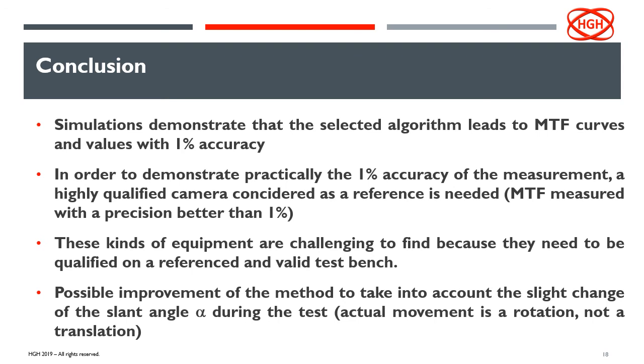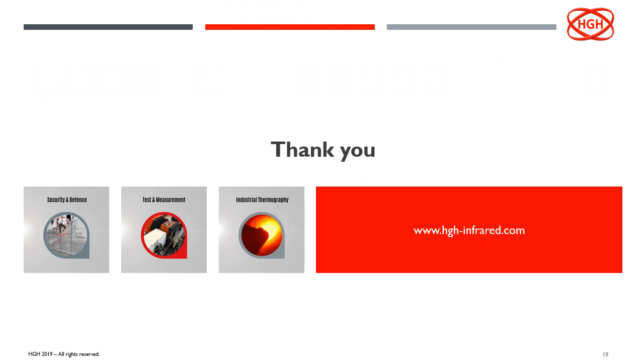In conclusion, simulations demonstrated that the selected algorithm leads to MTF values with 1% accuracy, confirming the method is valid. To demonstrate this accuracy experimentally, a highly qualified reference camera with MTF measurements from another bench at better than 1% precision would be needed — a real challenge. A possible improvement would be to account for the fact that the slant angle alpha of the knife edge is not constant during rotation, incorporating this into the algorithm to further increase accuracy. Thanks for listening; please contact us if you have any questions.